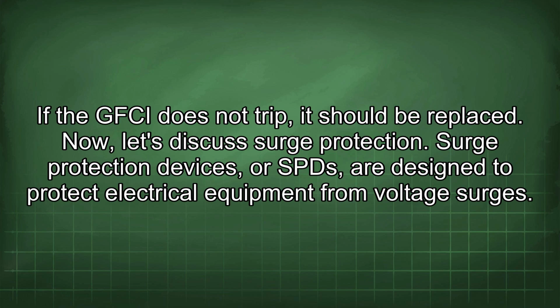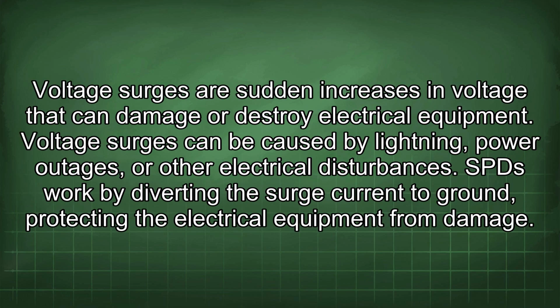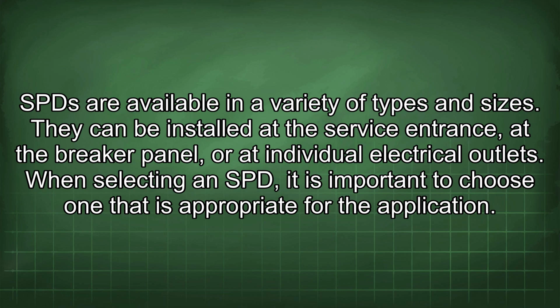Now let's discuss surge protection. Surge protection devices, or SPDs, are designed to protect electrical equipment from voltage surges. Voltage surges are sudden increases in voltage that can damage or destroy electrical equipment. Voltage surges can be caused by lightning, power outages, or other electrical disturbances. SPDs work by diverting the surge current to ground, protecting the electrical equipment from damage. SPDs are available in a variety of types and sizes. They can be installed at the service entrance, at the breaker panel, or at individual electrical outlets.